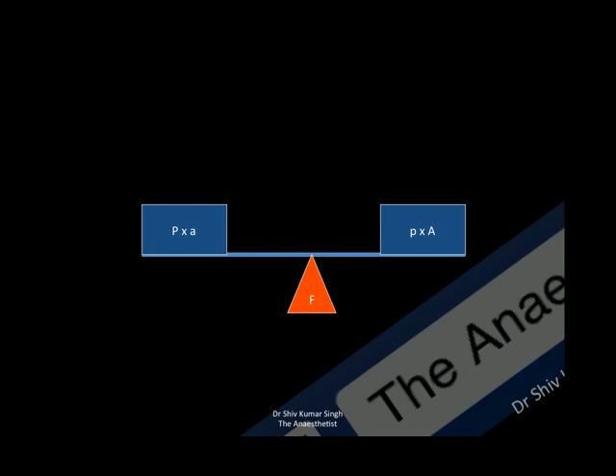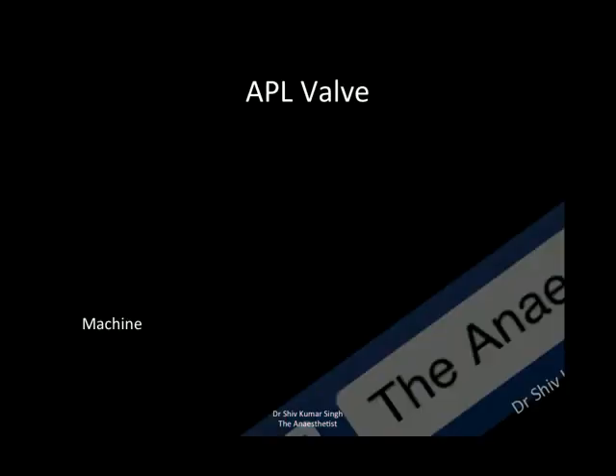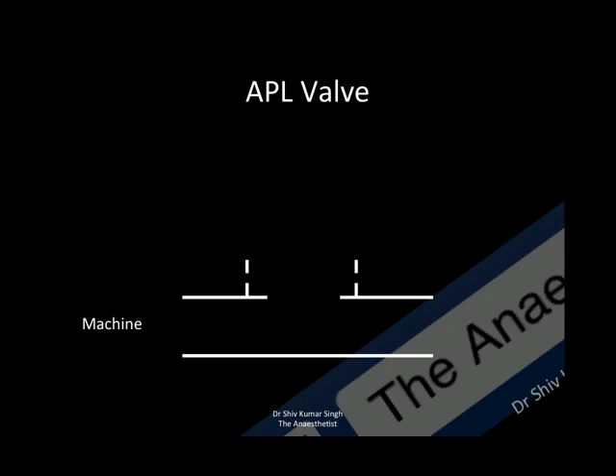This principle is used in many places in the machines and components of machines. One of them, used by everyone day in day out, is an APL valve. Looking at the components of an APL valve: it is nothing but a T-piece — you have the machine end, the patient end, and the expiratory port.